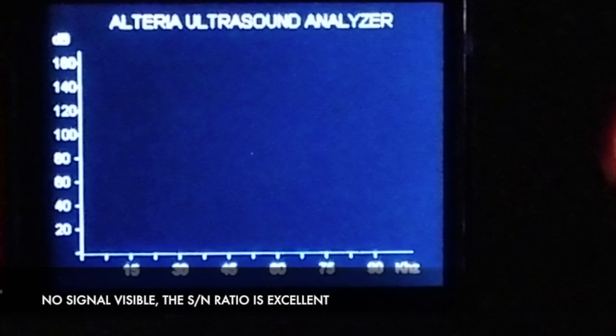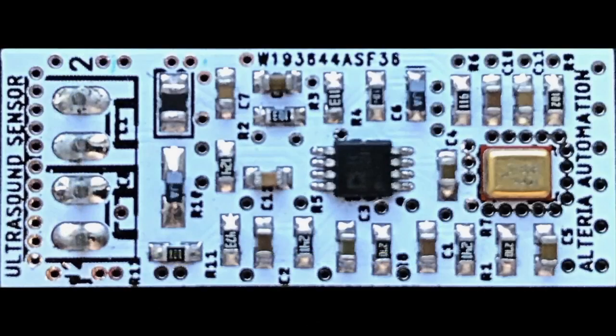And then I switch off the transformer. You see the signal to noise ratio is excellent. There is absolutely no signal when the transformer is off. And that's a big advantage of ultrasound compared to vibration. In vibration, you're going to experience a much worse signal to noise ratio.